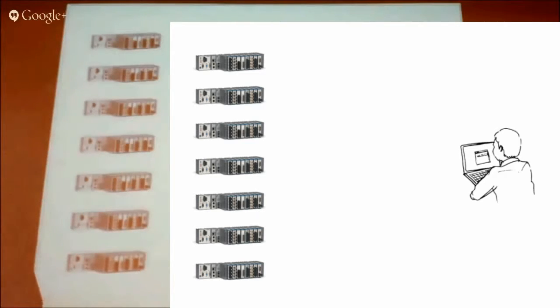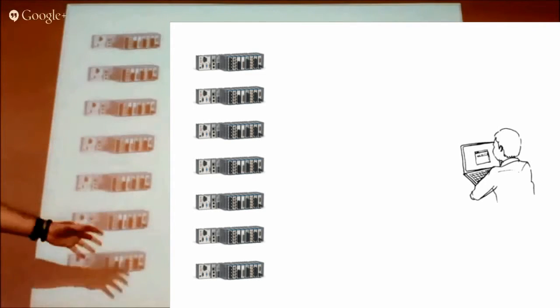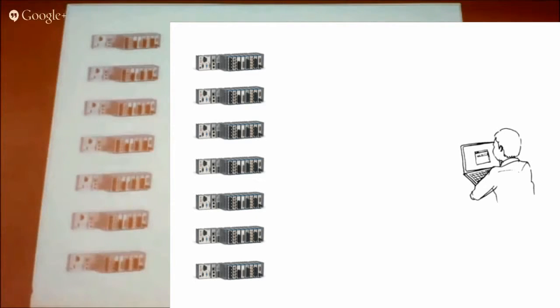It should be fair to say this is all power quality monitoring, basically. They refuse to call wind turbines and solar farms clean energy, because from an energy point of view, it's very dirty. It has lots of harmonics because it all pushes out DC and has lots of switching to convert it to AC, which causes their components to heat and potentially fail if left unchecked.